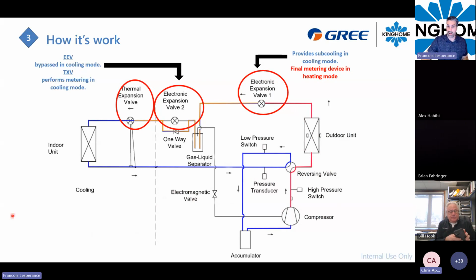Hey, Francois, can I just interrupt for a sec? There's a question, maybe a follow-up to the last question. Just asking, so no refrigerant in the condenser, only in the coils, or both? No, both. Perfect. Both. So the condenser as well, the service valve will be front seated. So you have all the refrigerant in the condenser coil, but in the indoor unit, the A-coil, for example, they had already 8 ounces of refrigerant.